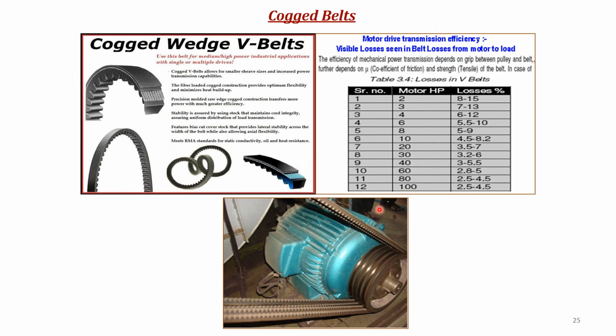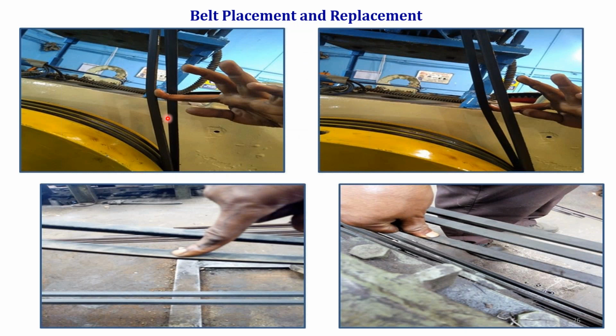And this is the recent type of cogged belt, which is a newer type. And these are some of the pictures which we took during the tensioning of the belt. When you press the belt, you can see there is a huge gap always available. And it's a best practice to maintain that the top portion of the belt, what you push, is almost equal to the bottom portion. There should not be a gap, so that the percentage slippage is going to be 1%. It's a thumb rule, but not an exact value.